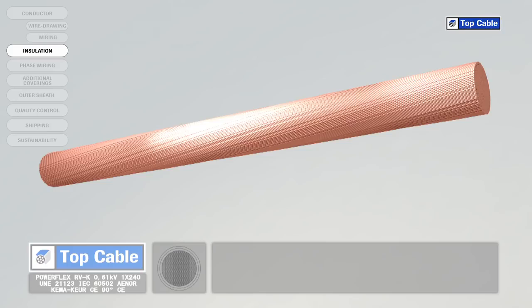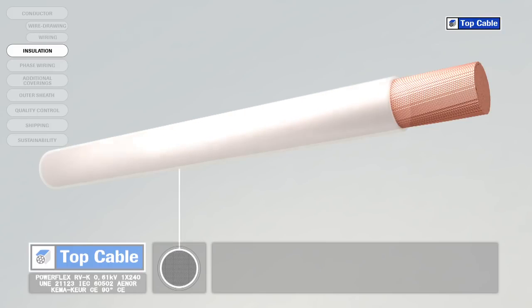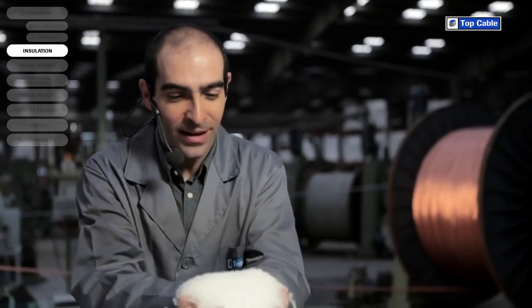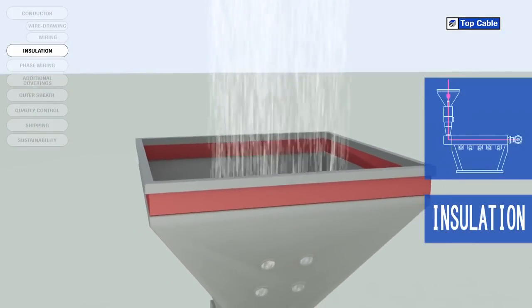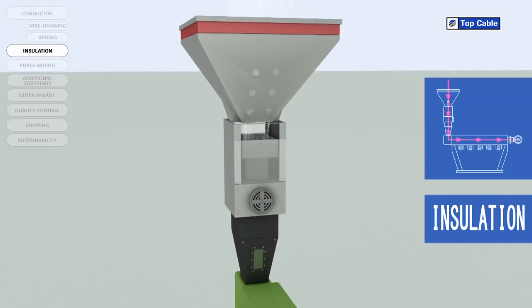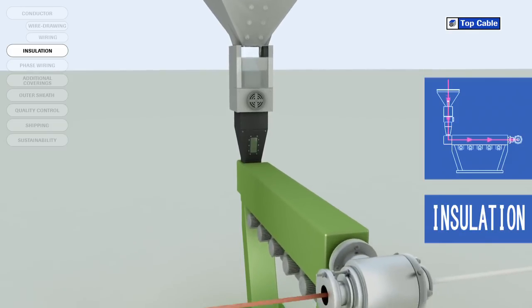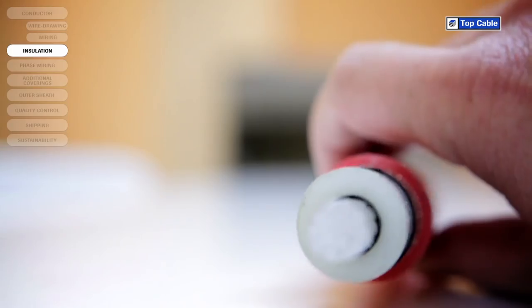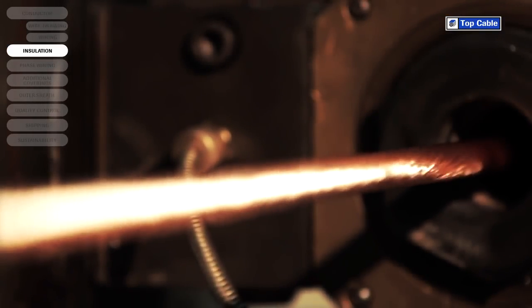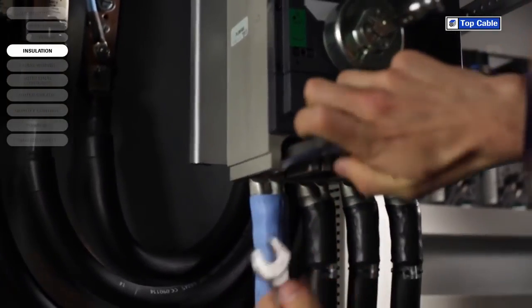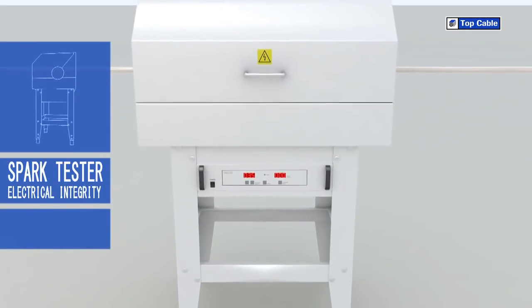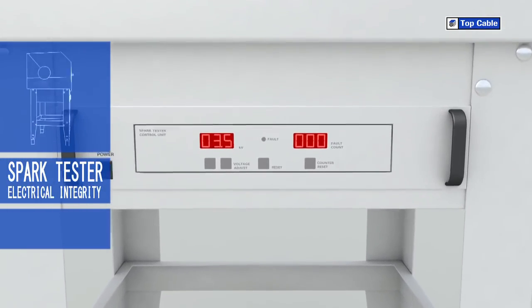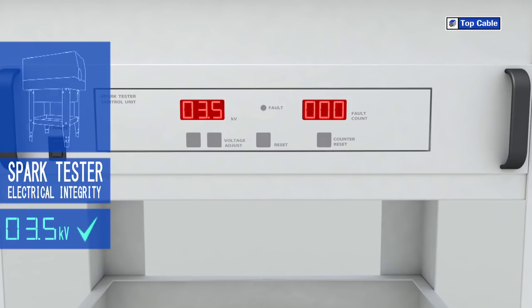The next process in the manufacture of electrical cables is the insulation. This is when we place an insulating cover over the conductor to prevent current leakages. The insulating material is added by a process of extrusion at high temperature. Several insulating materials may be used — PVC, EPR, XLPE, etc. — depending on the characteristics of the cable required. The quality of an insulation material depends on two basic characteristics: its insulation capacity and its heat resistance. The material's insulation capacity and its thickness determine the cable's maximum service voltage. An insulation material with a high heat resistance allows the conductor to transmit more power than the same cross section with an insulation with a lower heat resistance. The whole length of the cable undergoes a voltage test to ensure the insulation layer does not have any faults.